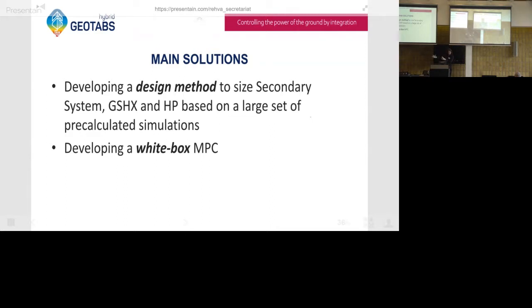So the secondary system, the ground source heat exchange, the heat pump. The way we're doing this is by running simulations that strategically represent relevant building types, sizes, and parameters, so we can cover the most important part of the relevant building markets. So if a designer wants to design such a building, they can fall back on pre-calculated results for a quick sizing, then do a detailed sizing once the contract has been awarded. That's for the design.